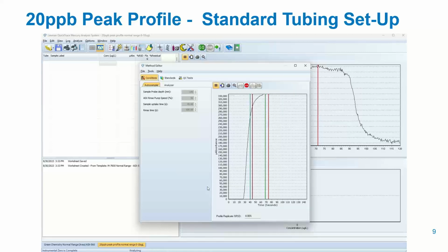Which is totally normal, by the way. This dip that's about to happen, right about here, yep, there it goes, is totally expected, because when the probe moves from the sample vial back to the rinse station, it's going to pull up ambient air into the system, and air is primarily made of nitrogen, which suppresses the signal.